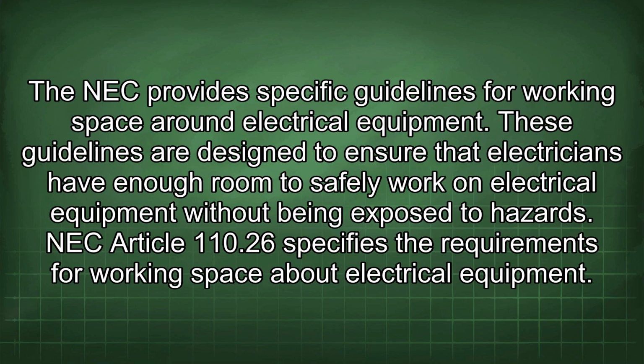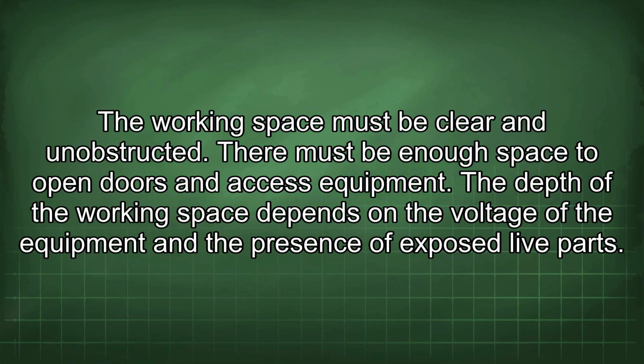The NEC provides specific guidelines for working space around electrical equipment. These guidelines are designed to ensure that electricians have enough room to safely work on electrical equipment without being exposed to hazards. NEC Article 110.26 specifies the requirements for working space about electrical equipment. The working space must be clear and unobstructed. There must be enough space to open doors and access equipment. The depth of the working space depends on the voltage of the equipment and the presence of exposed live parts.